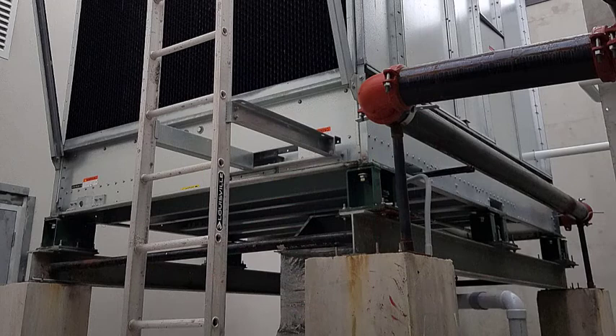My final conclusion on this site visit is that the isolators have been installed close enough to our installation requirements to be okay, but should they experience any vibration or noise problems in the spaces below the cooling tower, or if they need an installation certification, they will need to adjust the isolator at location 1 and ensure the top plate is floating and out of contact with the stanchions.